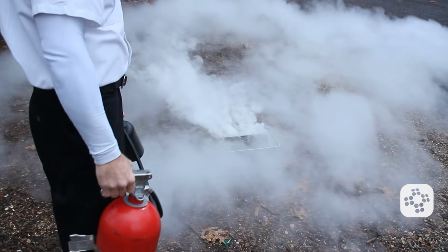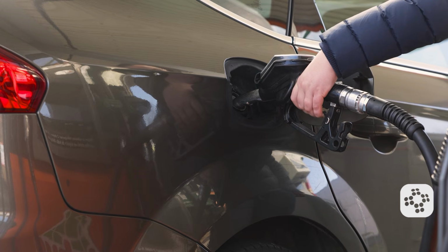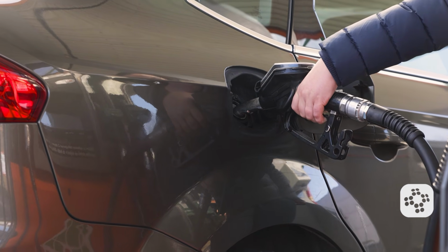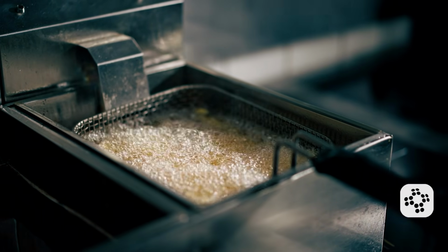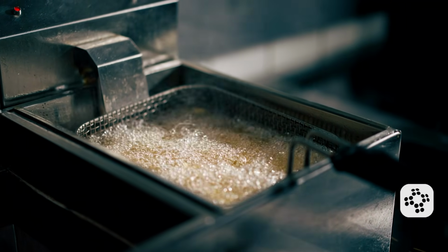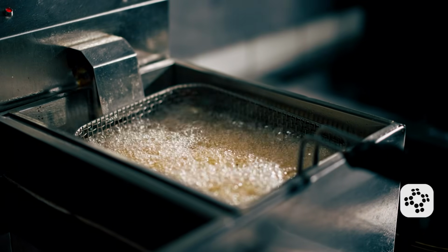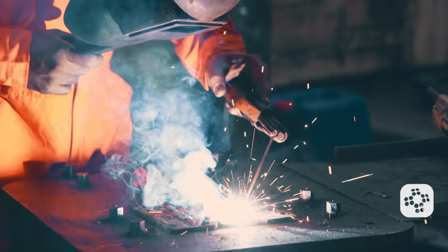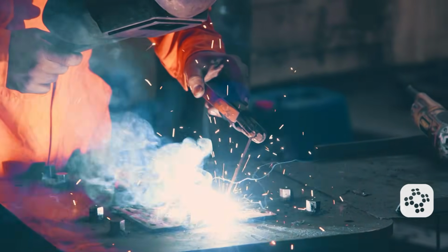Now, these are used for Class B and Class C fires. Class B fires involve flammable or combustible liquids such as gasoline, kerosene, oil-based paints, and solvents. Class K fires involve cooking oils and fats, are common in commercial kitchens, and require a Class K extinguisher. Class D fires involve combustible metals and are typically found in specialized industrial settings. A Class C fire, however, involves electrical equipment such as an appliance, wiring, or circuit breakers and outlets.